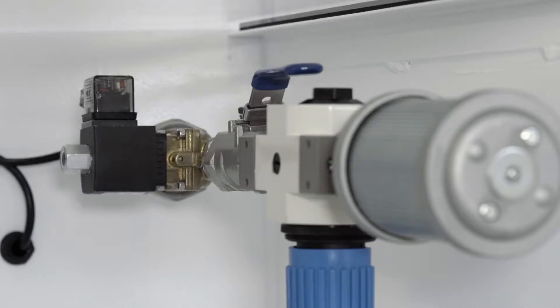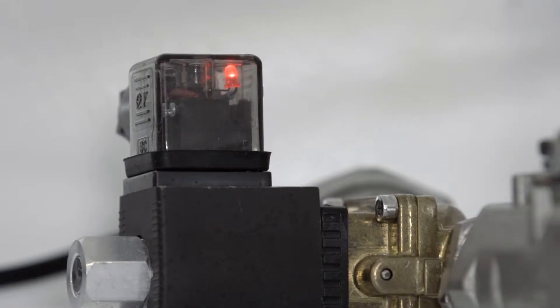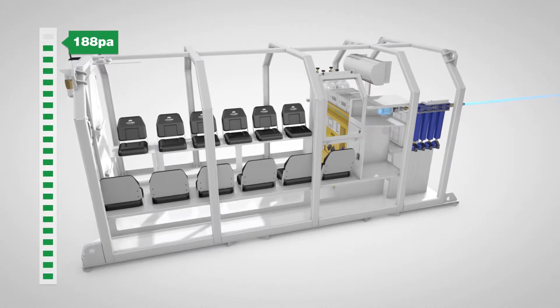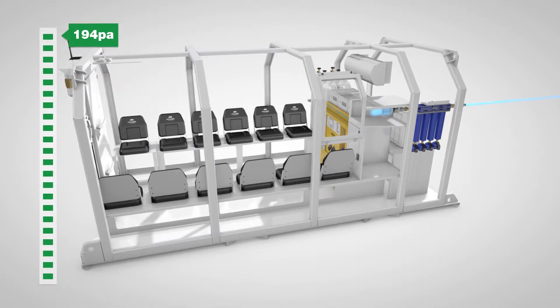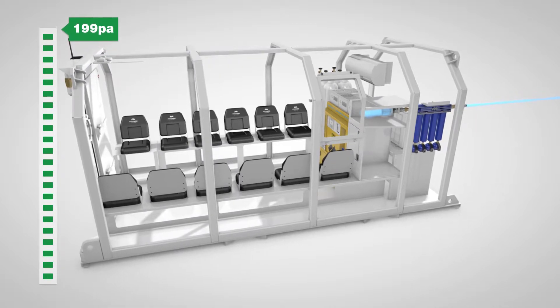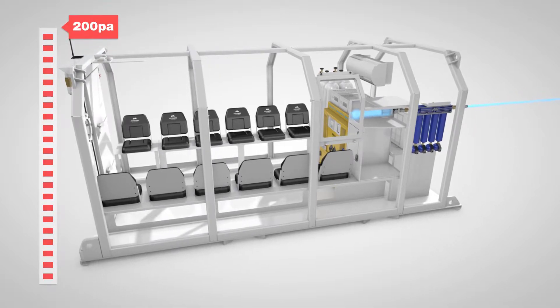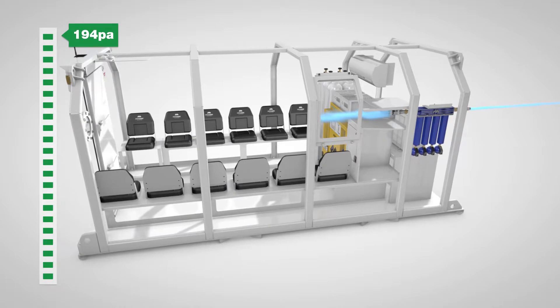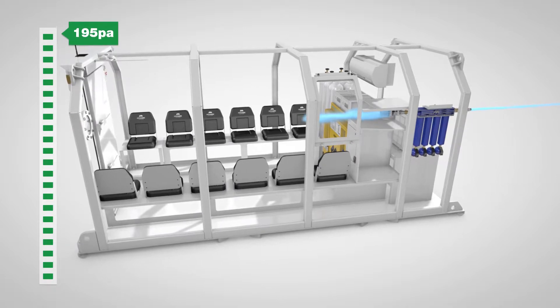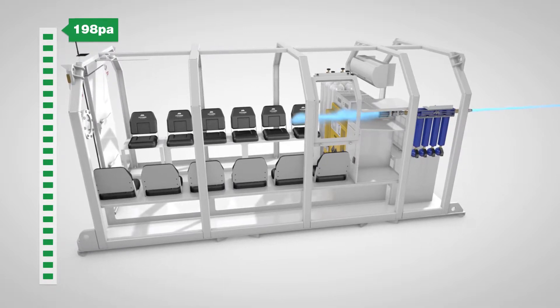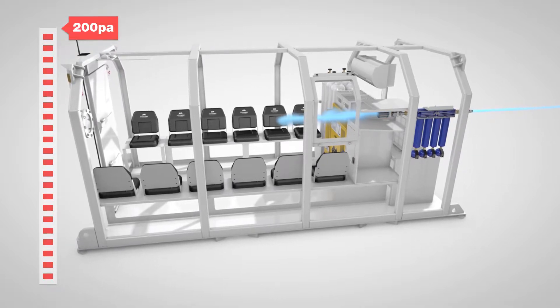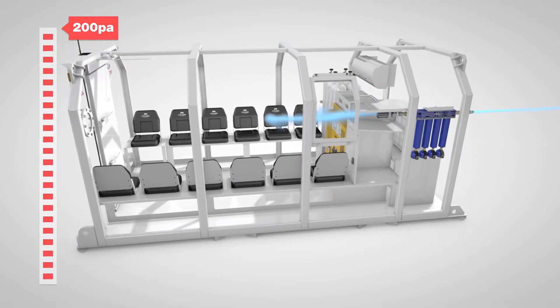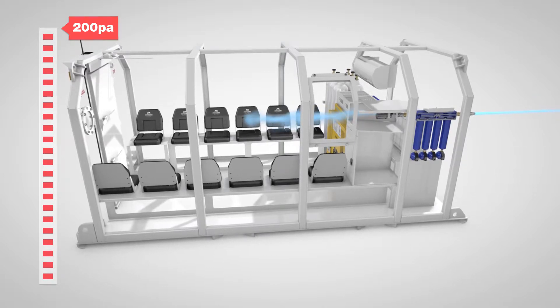Sensors within the chamber switch the air intake on and off, emitting periodic bursts of compressed air to maintain an internal pressure of 200 Pa. This creates a positive pressure seal, ensuring contaminants cannot enter the refuge chamber from the outside environment.